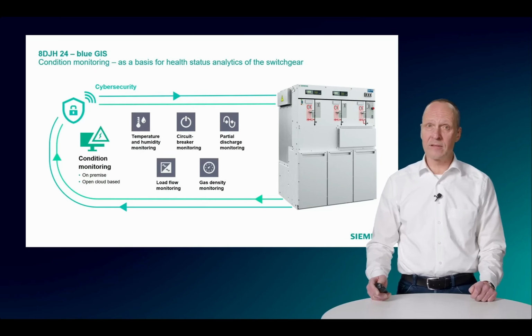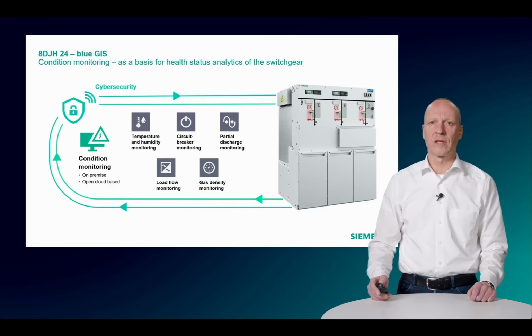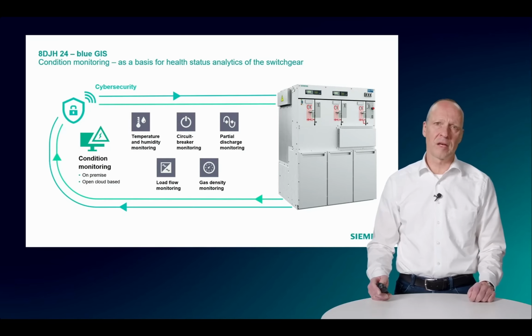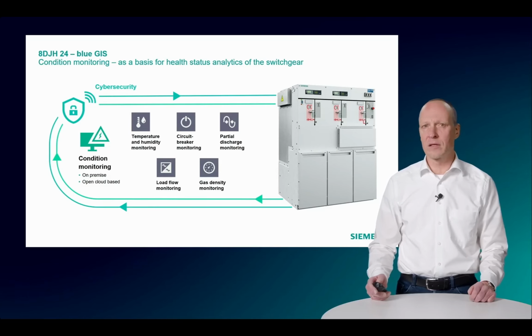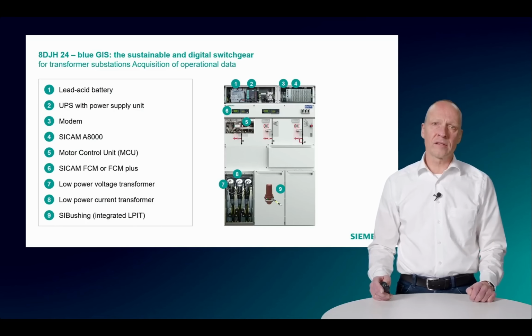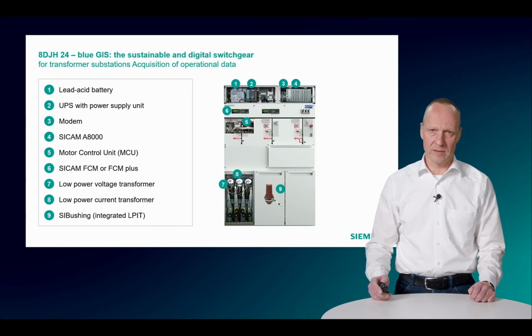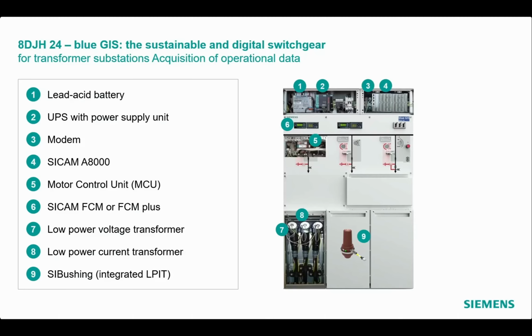Last but not least, a load flow monitoring based on current and voltage sensors connected to an intelligent short circuit and earth fault directional indicator like our SICAM FCM Plus or a protection relay from our SIPROTEC 5 family can be integrated. Looking at the secondary GIS, especially our 8DJH24 Blue GIS, digitalization involves so-called smart ringmain units. This slide here shows the devices and sensors integrated in our smart ringmain unit solution.